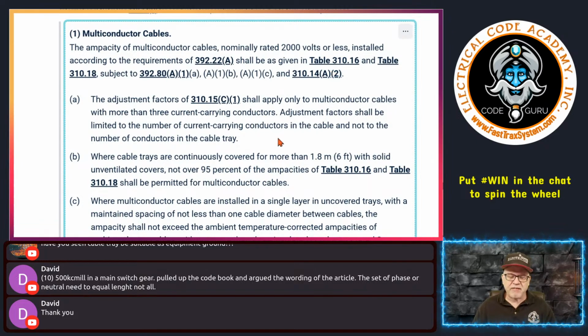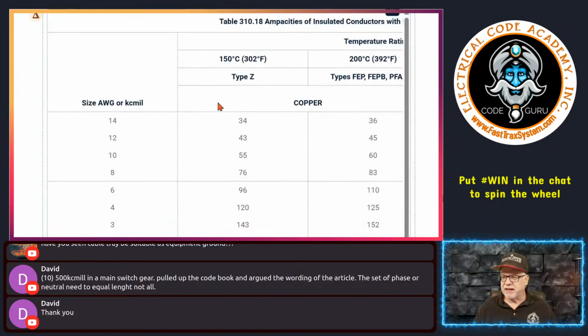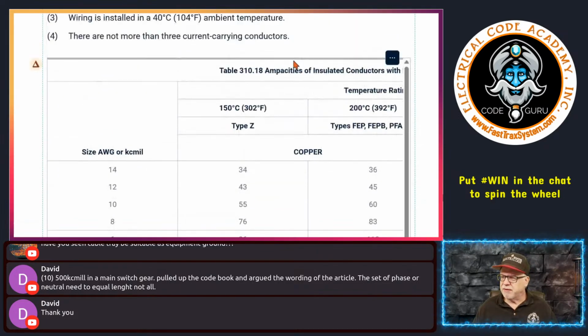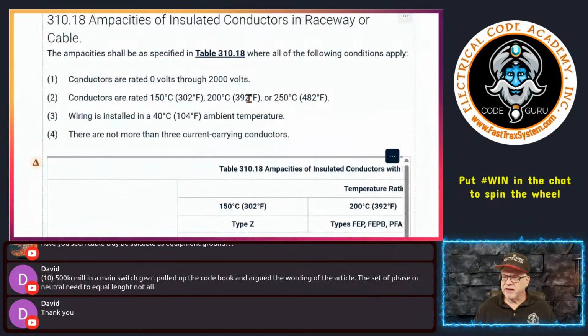310.16 is our basic table for ampacity. So that's the first thing I tell folks right off the bat. When it comes to multi-conductor cables in a cable tray, for the most part, you're going to be using 310.16 ampacity values, flat out, okay? Now, 310.18 is different types of cables, right? So if you go look at 310.18, I'll pop that up here.